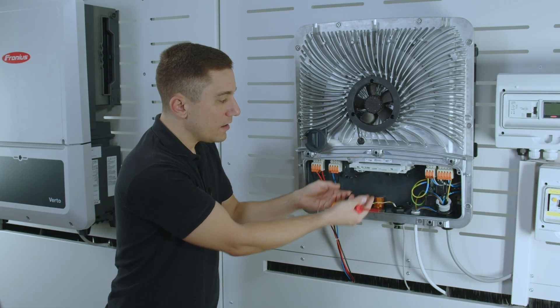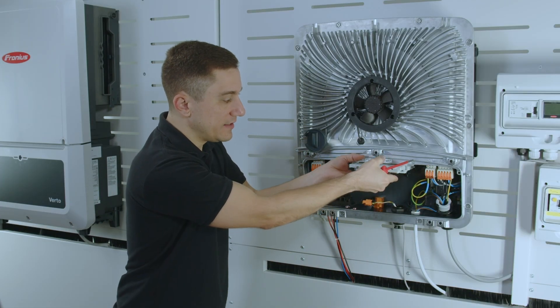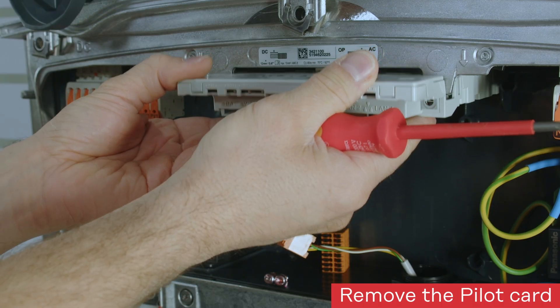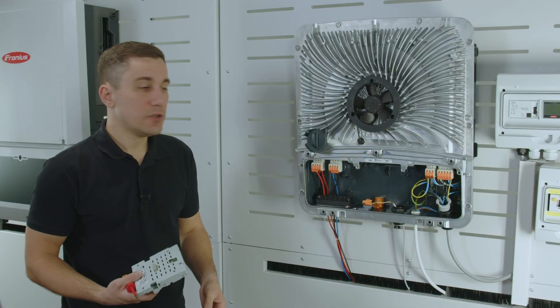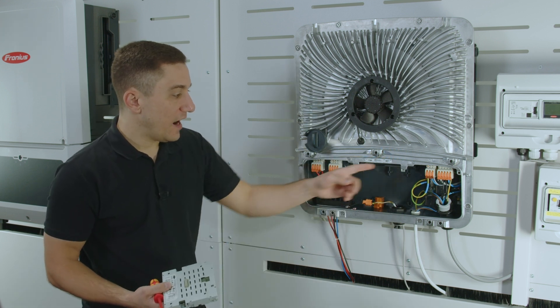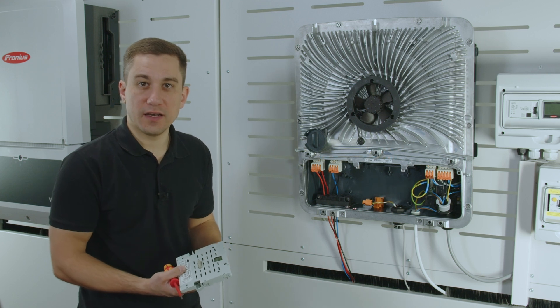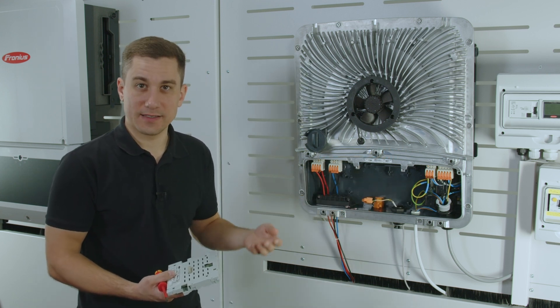To remove the pilot card, this is just a component with a plug, so you just need to undo it to the bottom side and remove it from the inverter. After you have a new pilot, you can build it in the same way in reverse: plug in the pilot card again, fasten the screws, replace the separation cover, place it again inside the inverter, and connect your data communication plugs again.